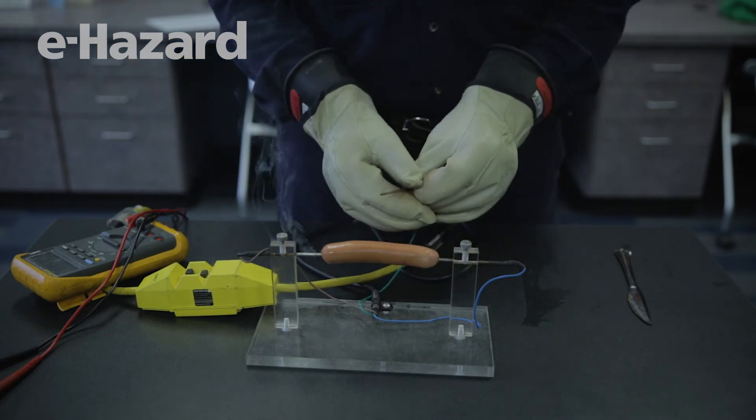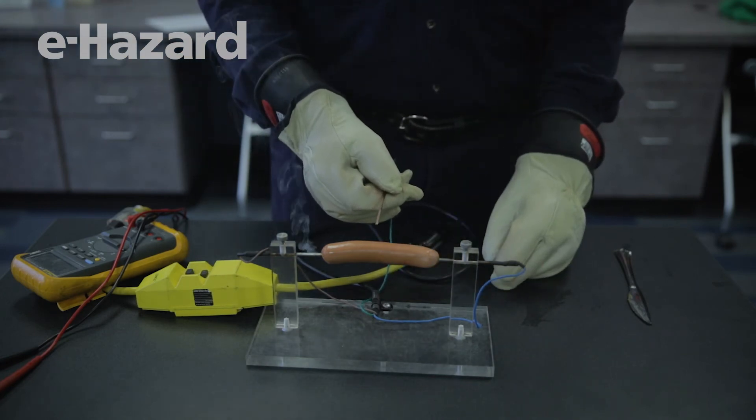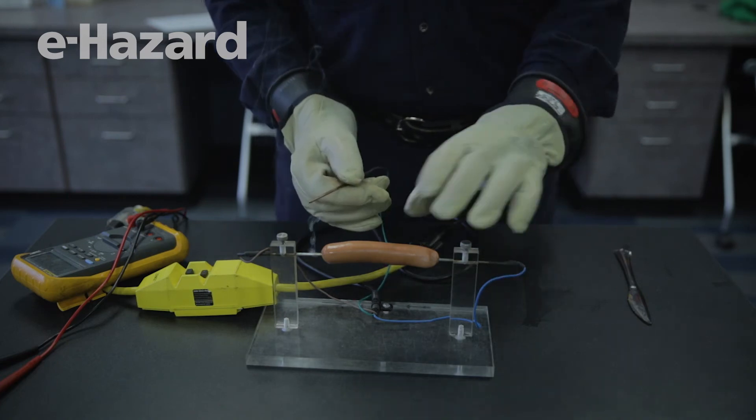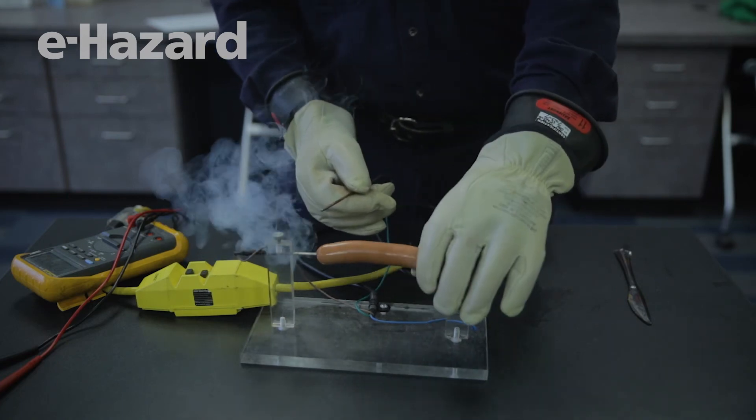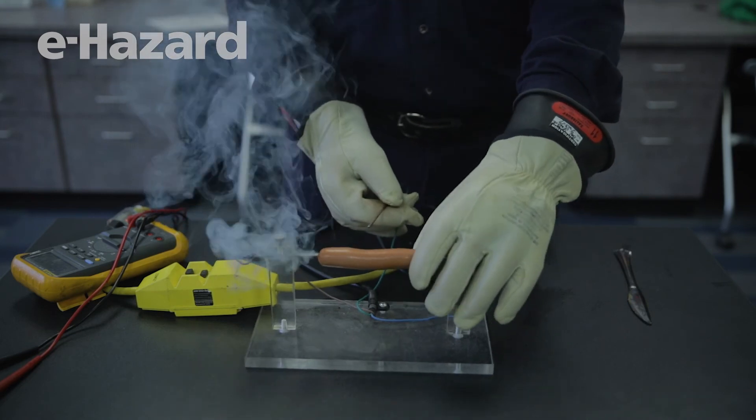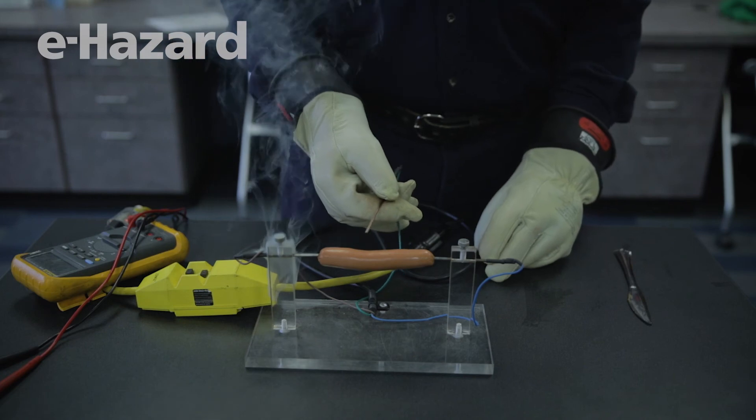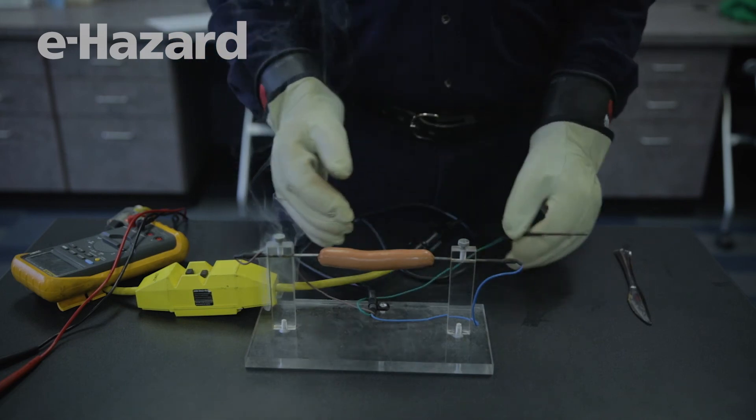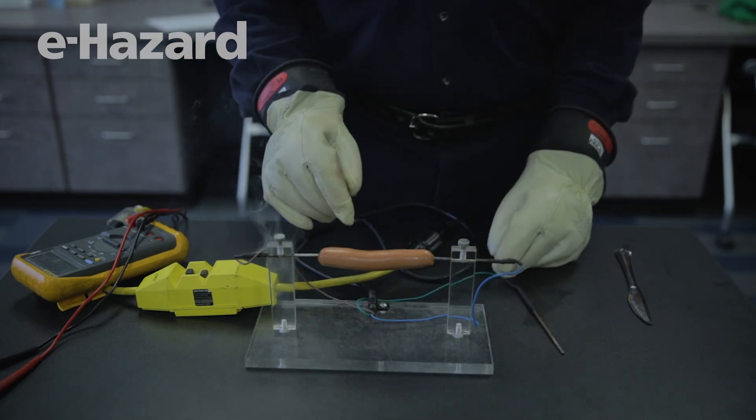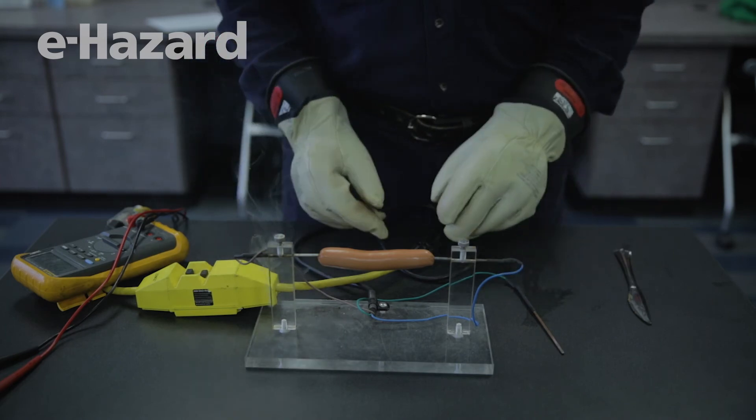So let's look and see what happens as soon as I establish a ground. I should hear my GFCI trip, right? Charlie's sitting here just cooking away, but externally, do you see anything? No. Watch. Did you hear the GFCI trip? As soon as I got a ground circuit, my GFCI tripped.